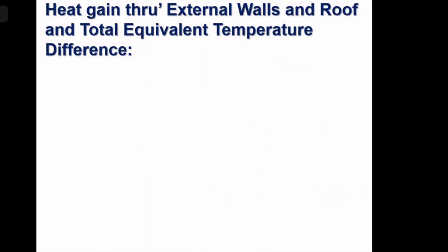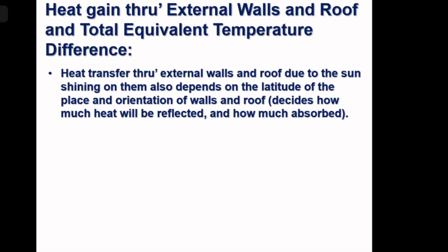So we will be replacing delta T. Instead of the temperature difference, we'll be using a term called total equivalent temperature difference to take care of all these phenomena. And all these phenomena will vary depending upon the building material construction. So if you are using a heavy wall, it will take longer to get heated up and longer to get cooled down. So that will have a different kind of phenomena.